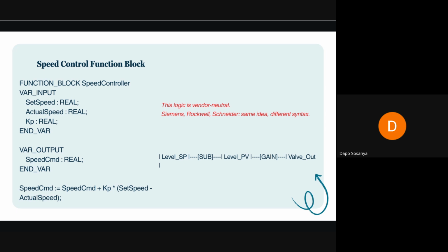So the system is continuously reading the value of the encoder. It takes the value, your set speed, and subtracts it from the value of the encoder. So this value inside this bracket could either be minus or plus. Whatever that value is, it multiplies it by this KP and then adds it to the existing speed command, the default speed command. So that gives it the speed command at that time. And then the process goes through the scan again - it scans continuously and continuously updates this speed command.